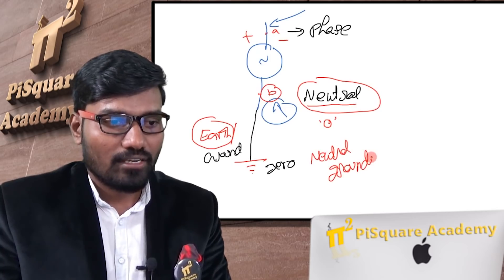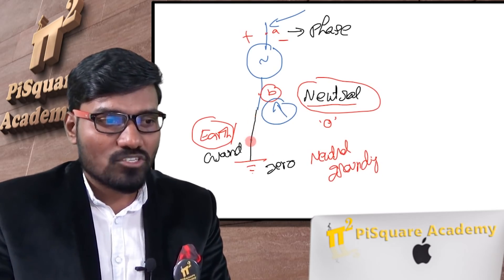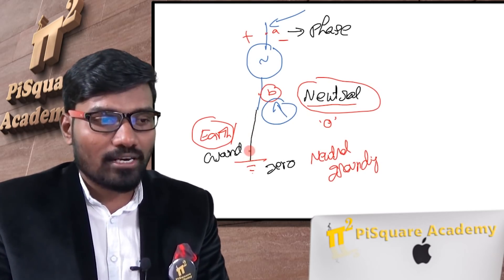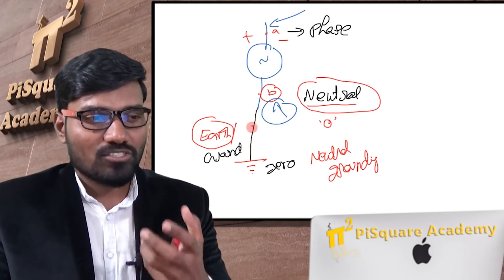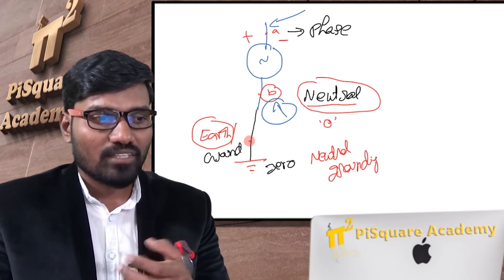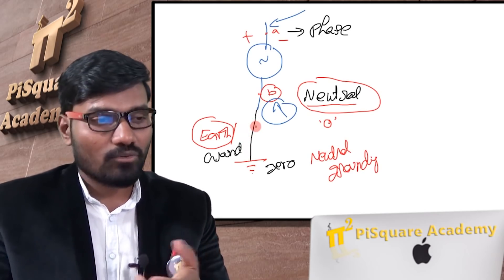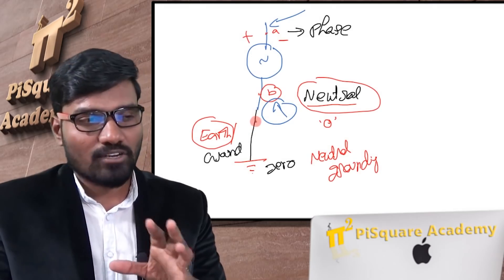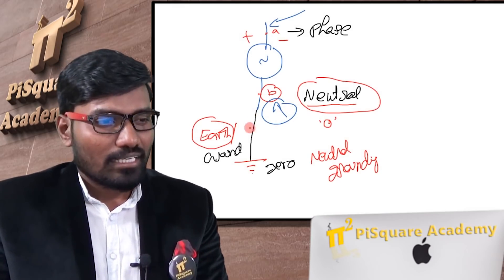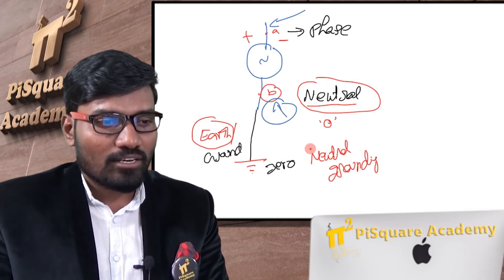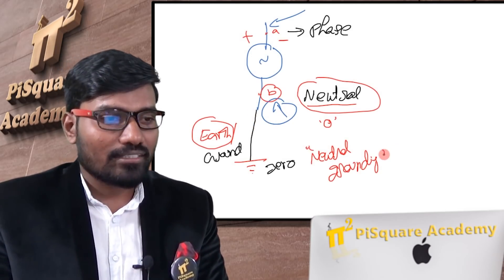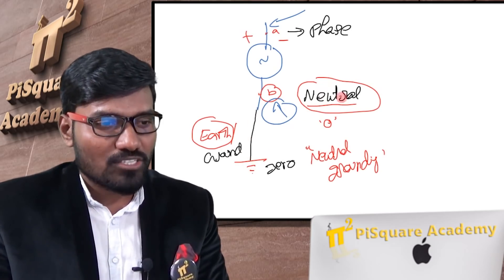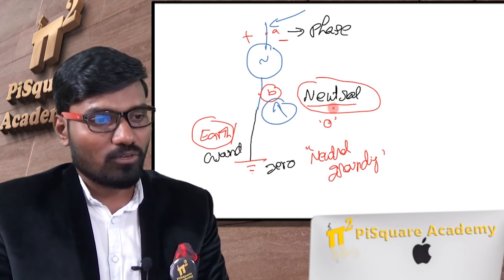Instead of connecting the neutral directly to ground — which is solid grounding — you can keep a resistance, called resistance grounding, or reactance grounding, or Petersen coil grounding. There are different types of neutral grounding. Neutral grounding means connecting the neutral wire to the ground to maintain neutral potential at zero volts.